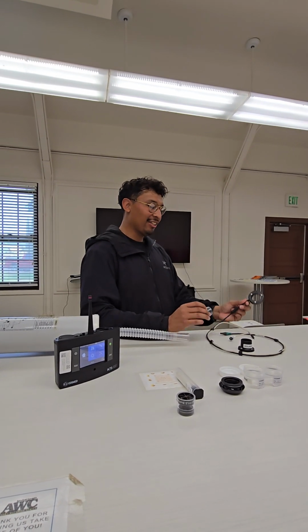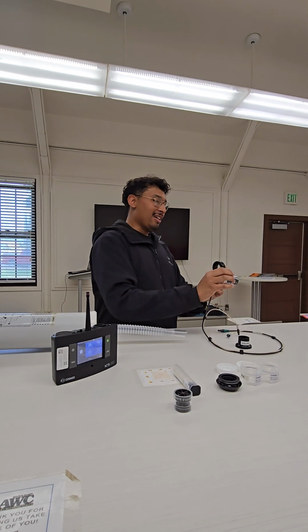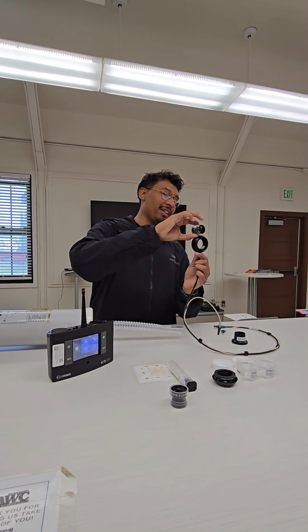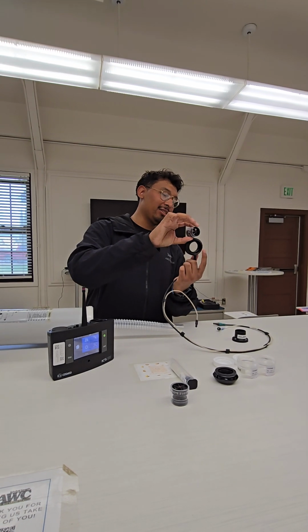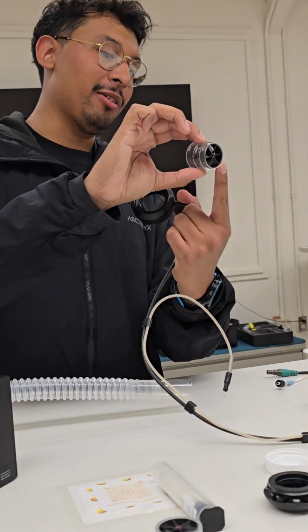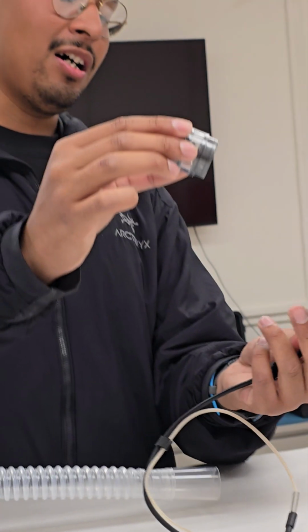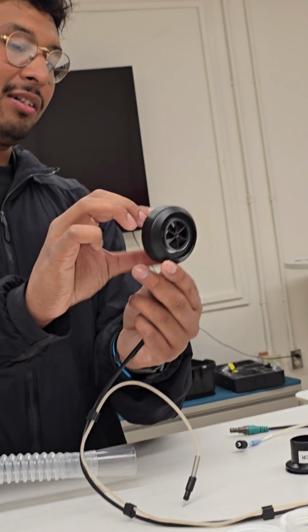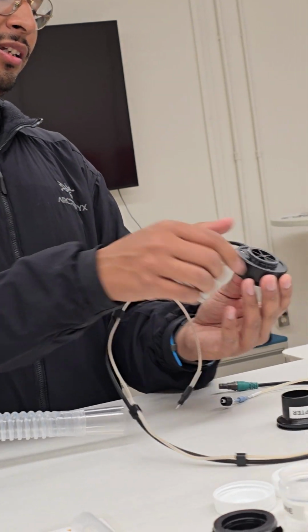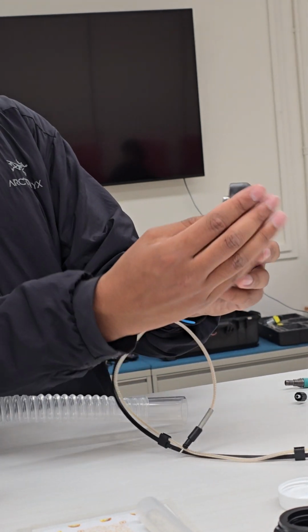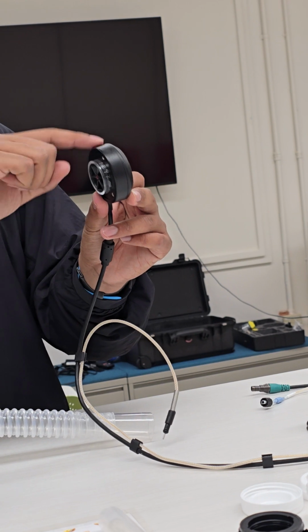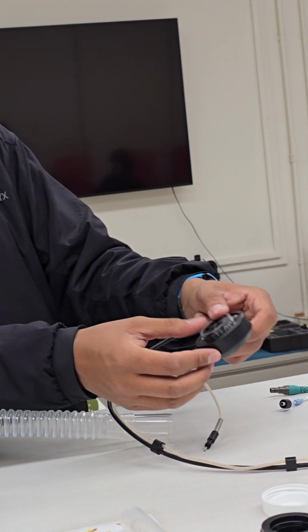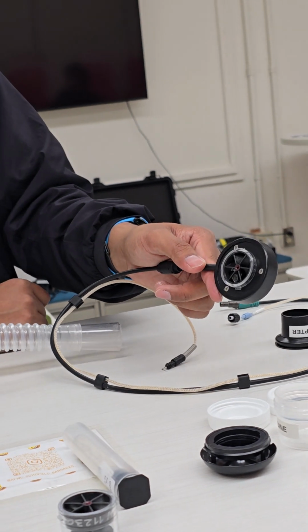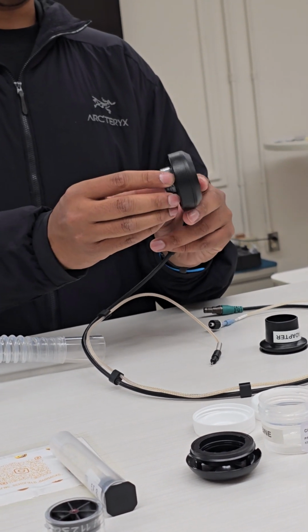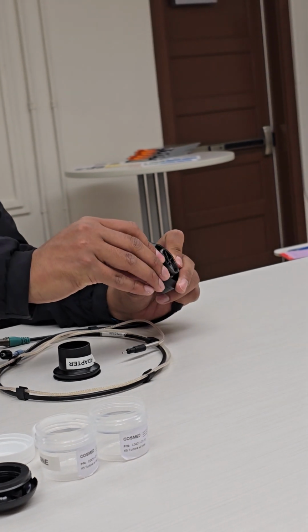So once again, optoelectronic reader. You have the turbine. Notice that they both get smaller on the front side. So this end is smaller than this end, and the turbine, same thing. Basically, just plug the turbine in from the back and slot it in, and then it should sit on the ring perfectly. If it's slightly out, that turbine is probably not being picked up by the reader. So just make sure that it's sitting all the way onto that optoelectronic reader. Yeah, that's pretty much it. Just push it all the way in.